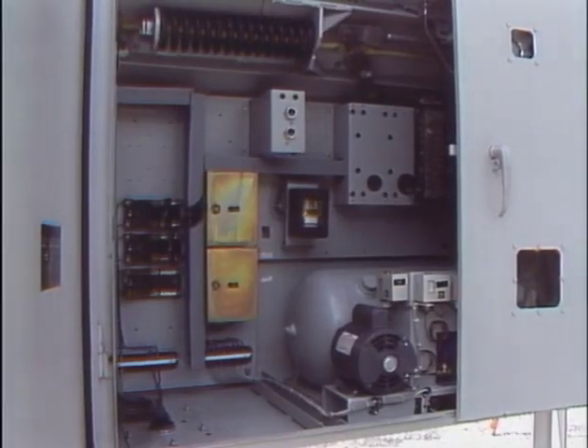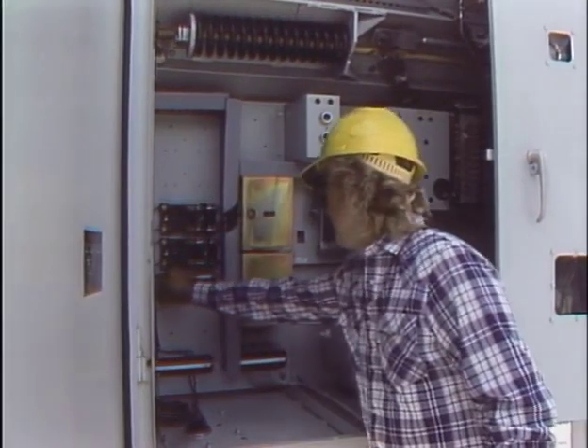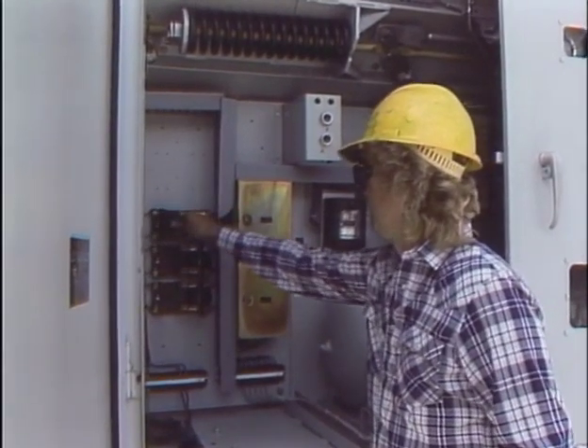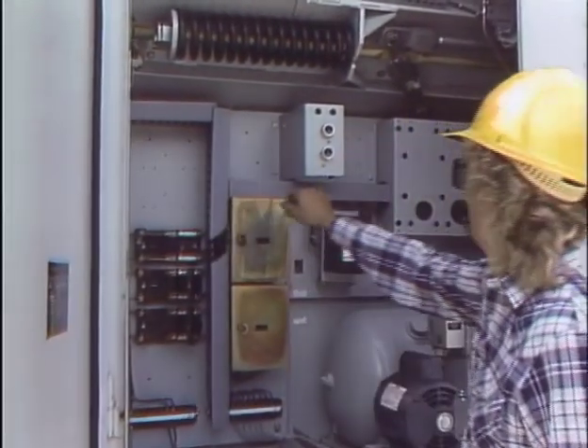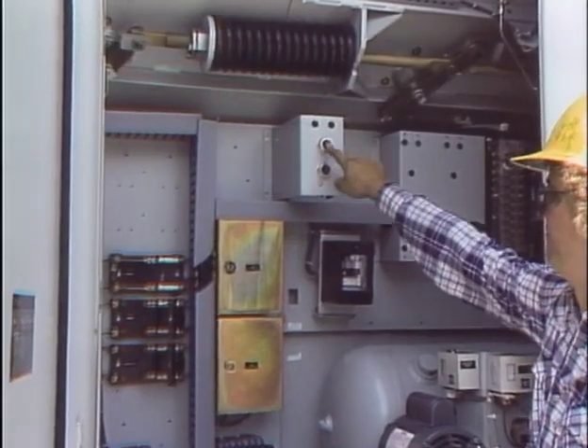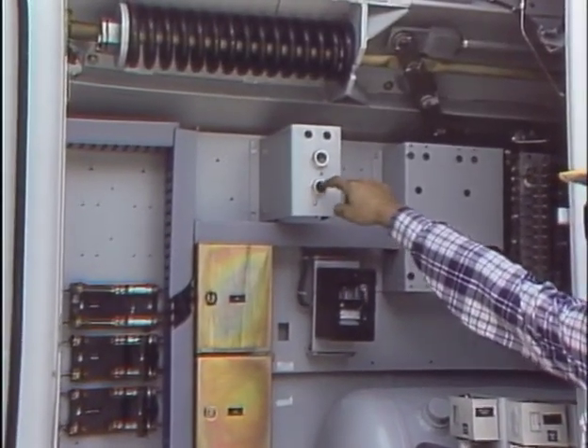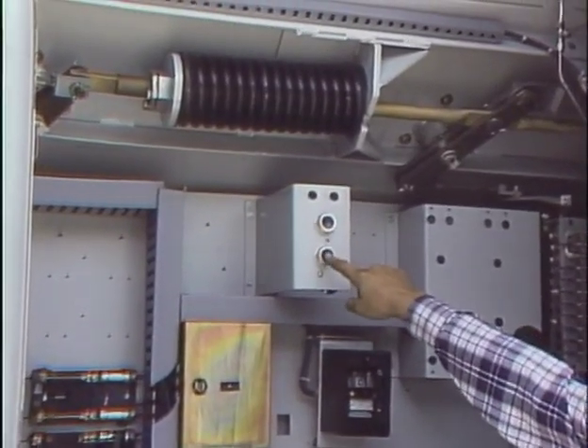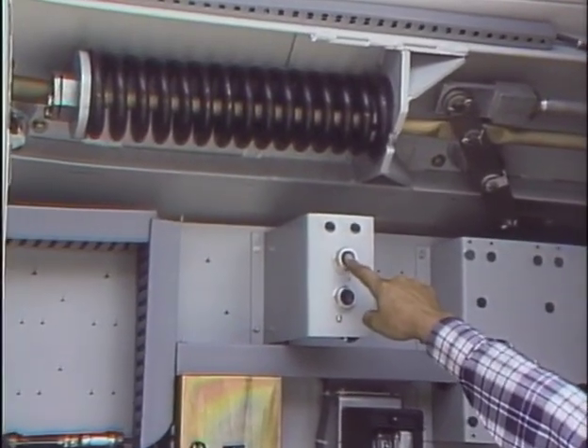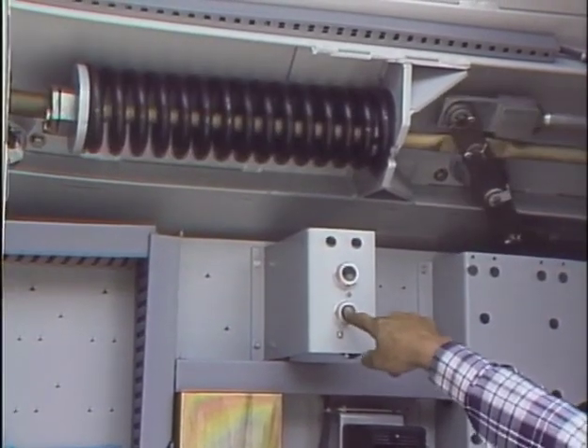Both the pneumatic and hydraulic operating mechanisms are also checked for their operating capacity. Operating capacity is defined by how many times the breaker can be operated without recharging the compressed air tank in a pneumatic mechanism or the hydraulic fluid system pressure in a hydraulic mechanism.